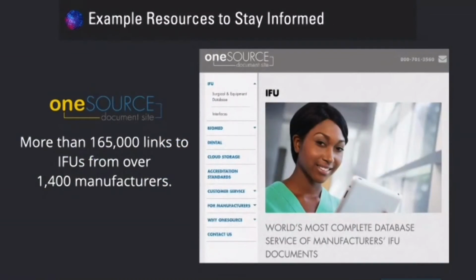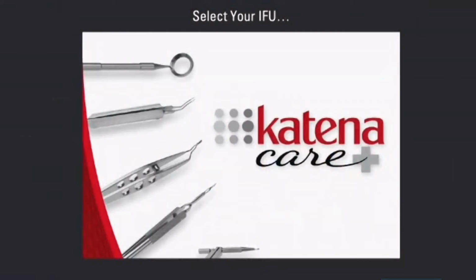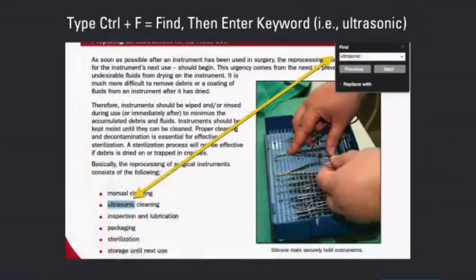OneSource is a great resource, with 165,000 links to IFUs from over 1,400 manufacturers. Now there's a bevy of information. Well, how can you cut through that? For the example of cavitation, here's an example of an IFU from these ophthalmic instrument companies. You have the need to find out something about your cavitation process, your ultrasonic cleaning. I'm not suggesting not reading your IFU, but if you really want to cut to the chase, you can type Control F for find on a PC, or Command F on a Mac.